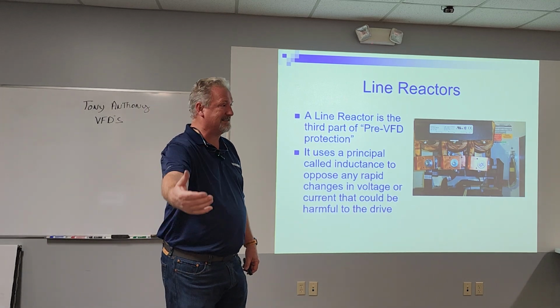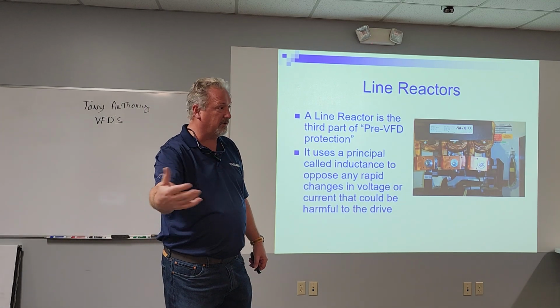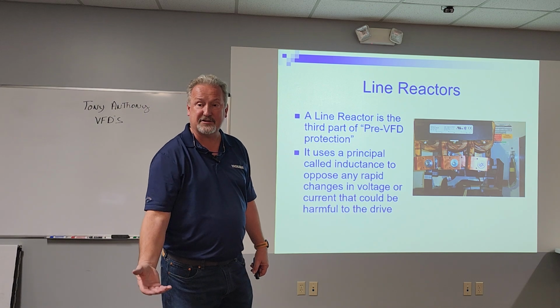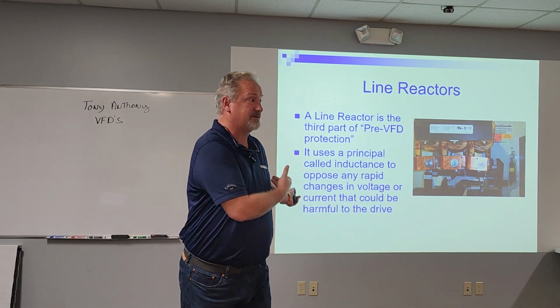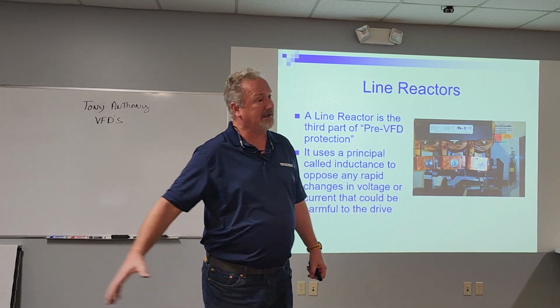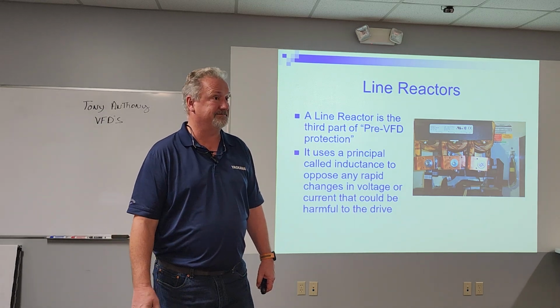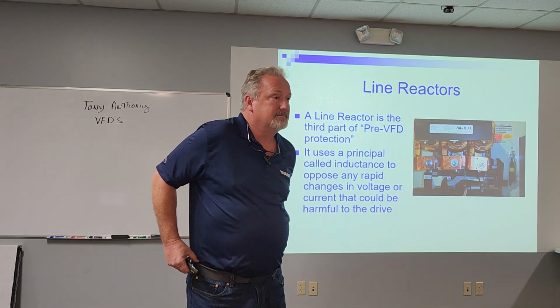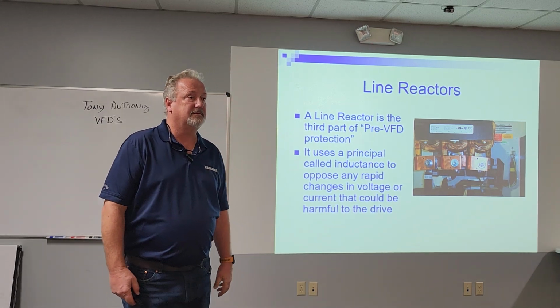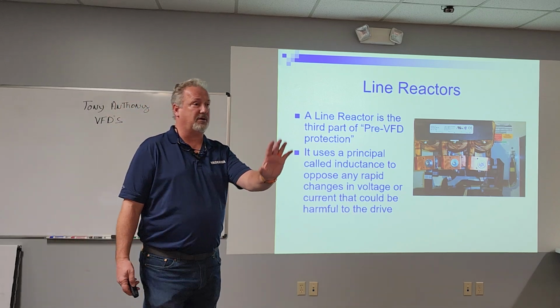Especially if they put a decent sized drive, or put 4, 5, 20 horsepower drives in, and all of a sudden they start having issues, they're probably having some harmonic issues because they've added some more guys topping off their tank. Now, do they use line reactors on the individual unit or on the transformer? No, on the drives. I'm sorry, on the drives, not the transformer.